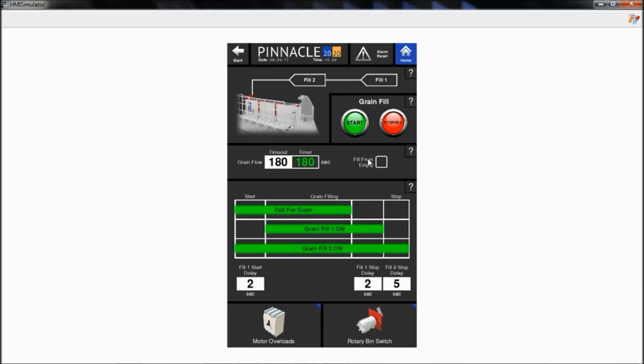So we'll go into our grain fill settings, and there's a new portion we added here called the Fill from Empty. The reason for this button is that anytime your fill is active, we monitor to see if the dryer is full. And if we see that the dryer is not full for a given period of time, labeled here as our grain flow, we have it set currently to 180 seconds or 3 minutes. If we don't detect grain at the top of the dryer for 3 minutes, we're going to assume that you've run out of corn.